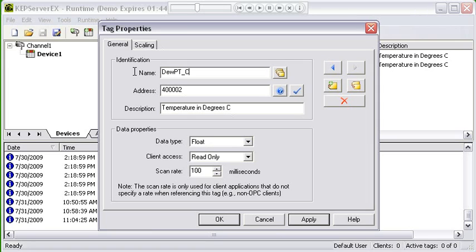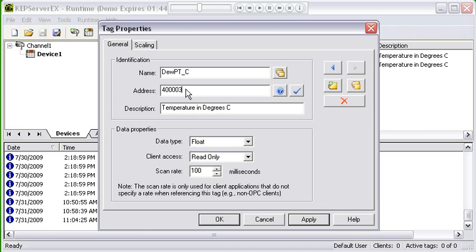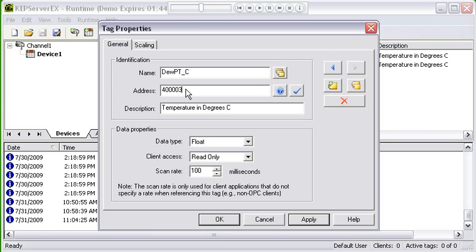It's also in degrees centigrade, and this is at holding register 3. A quick note on the addressing here: the Modbus registers are 16-bit registers and the data is floating point data. Floating point data is 32-bit data and therefore spans two registers within a device. If I had used the next consecutive address, I would actually be getting part of the data from the temperature showing up in my dewpoint. It's important that you are aware of how data is spread out or entered into your device.